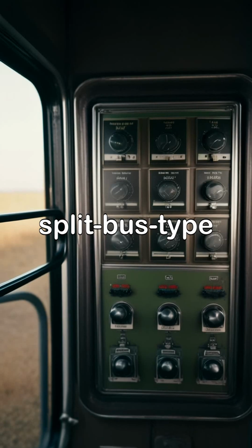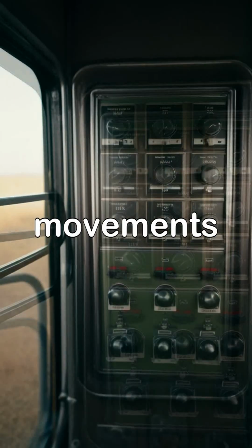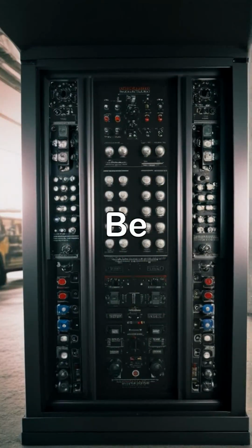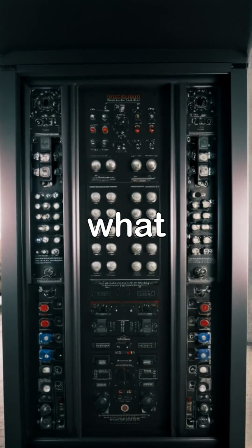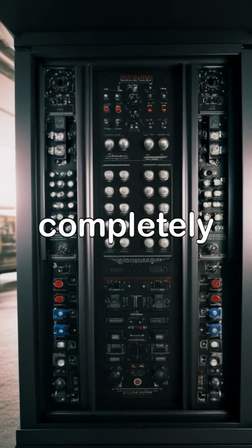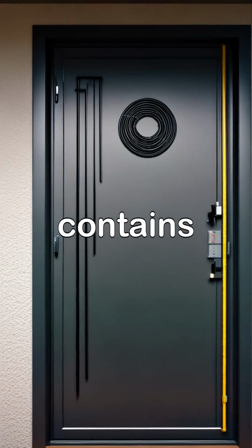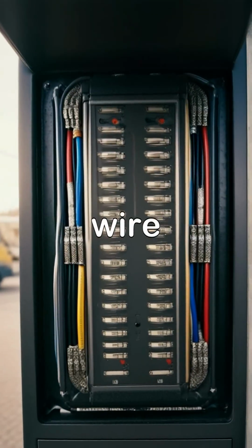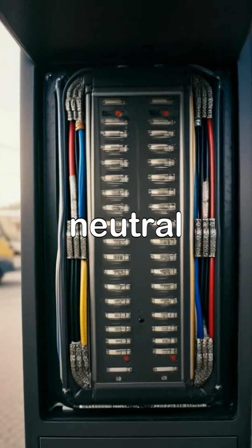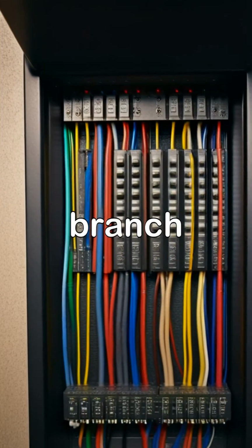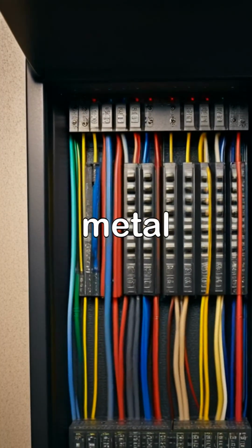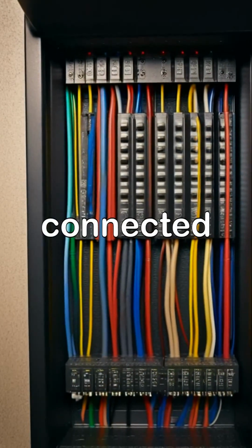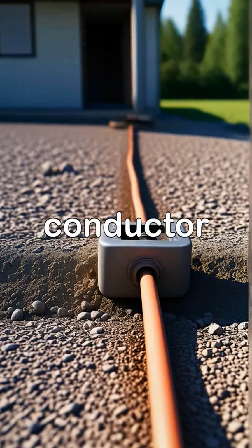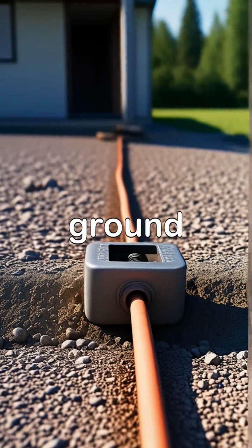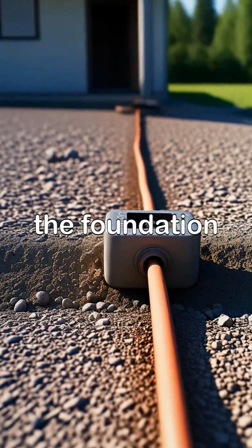With some old split bus type panels, you may need up to 6 separate hand movements to disconnect all the incoming power. Be sure you know what type of panel you have and exactly what steps you must take to disconnect the power completely. The service entrance panel also contains the grounding electrode conductor, an important wire that grounds the entire house. The neutral wire inside the service panel goes directly to the neutral bus bar. All the neutral wires of the branch circuits connect to terminals on this solid metal bar that is bonded, electrically connected, to the cabinet. The grounding electrode conductor connects the neutral bus bar to a metal ground rod driven into the ground beyond the foundation of the house.